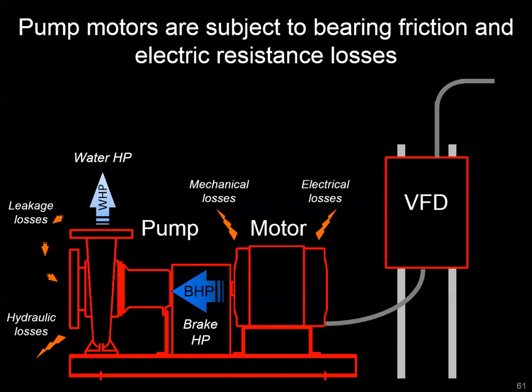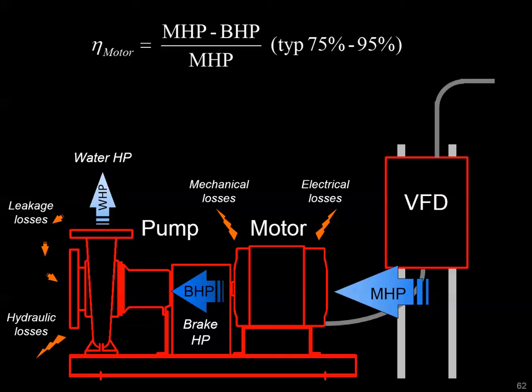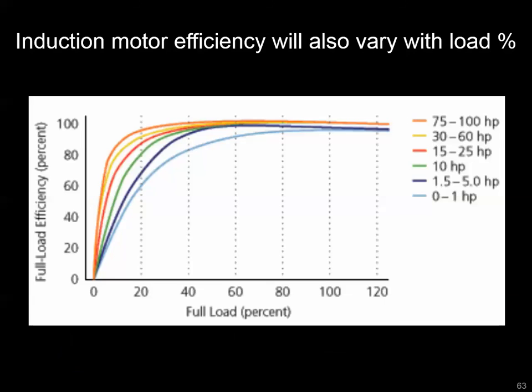The motor also has its own inefficiencies: mechanical losses from friction in the bearings, and electrical losses from resistance in the windings — those I-squared-R resistive losses. This requires additional energy supplied as motor horsepower to provide the needed brake horsepower. Keep in mind that with induction motors, efficiency drops as you move further from full load, becoming significant below about 50 percent load. If your pump frequently runs below that threshold, you'll see efficiency drops commensurate with motor size.